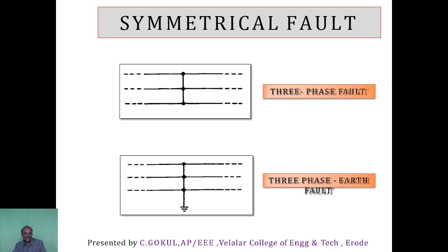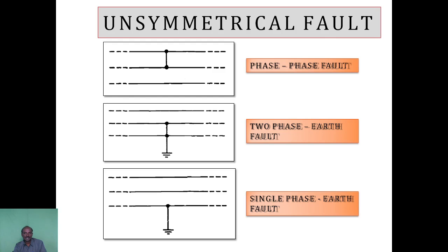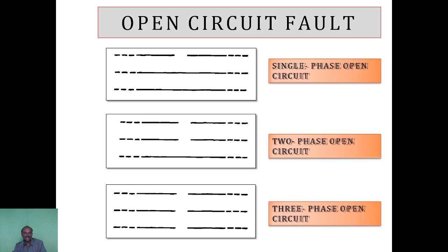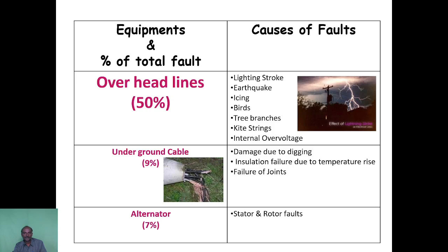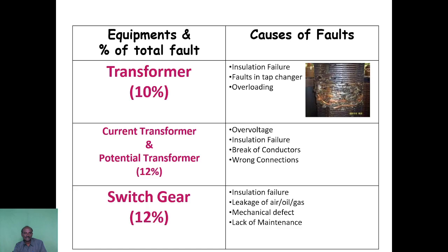Symmetrical faults are three-phase faults. Unsymmetrical faults we have different types. And also breaking of the conductors. That is categorized as open circuit faults. Single phase open circuit, or two phase opening of any two of the lines, or all the three phases. So various equipments and how they are being affected by the faults.